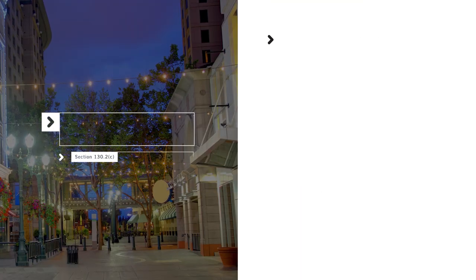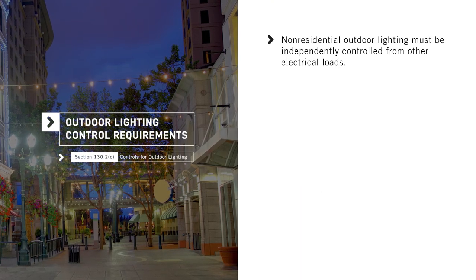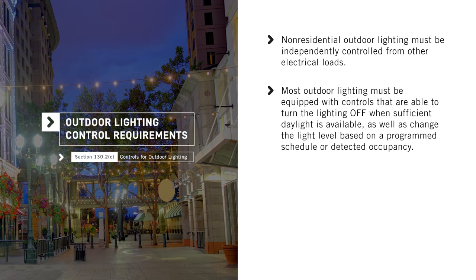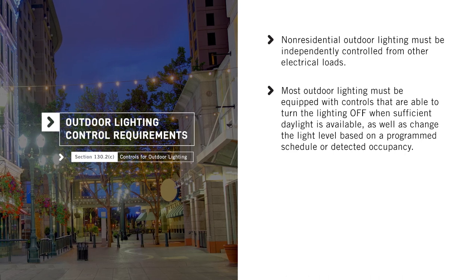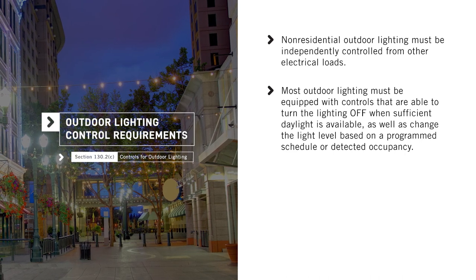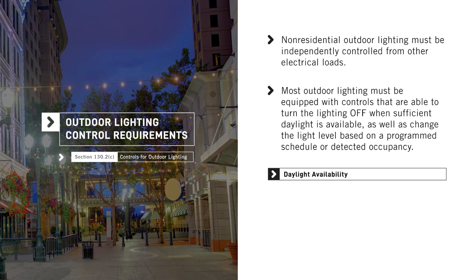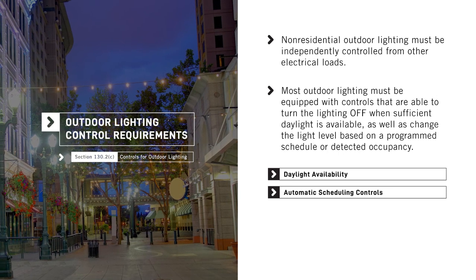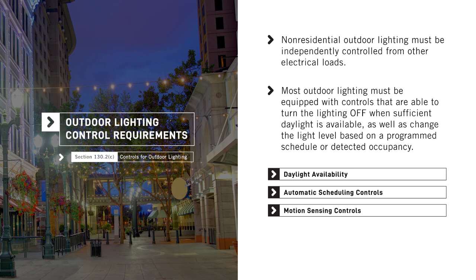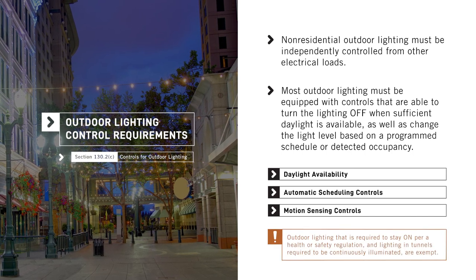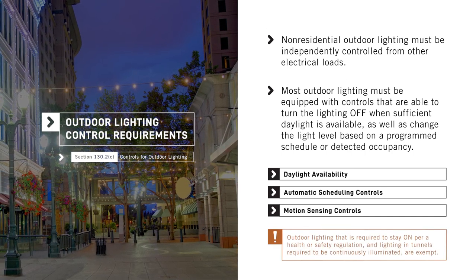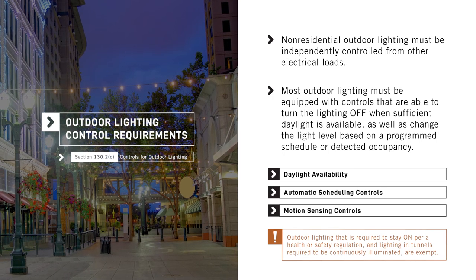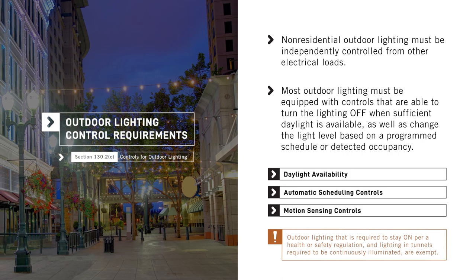The Energy Code requires that non-residential outdoor lighting be independently controlled from other electrical loads, and that most outdoor lighting be equipped with controls that are able to turn the lighting off when sufficient daylight is available, as well as change the light level based on a programmed schedule or detected occupancy. Exceptions include outdoor lighting required to stay on per a health or safety regulation, and lighting in tunnels required to be continuously illuminated.